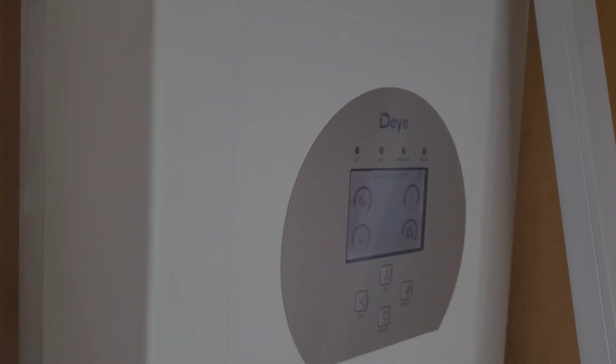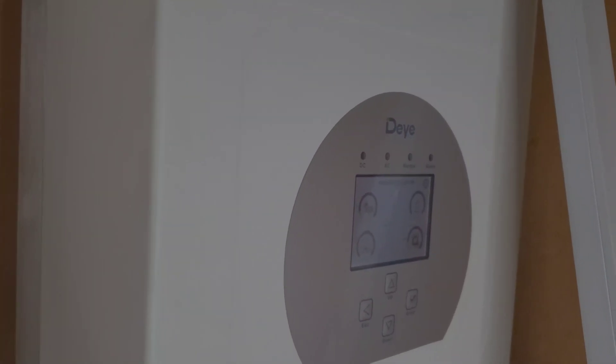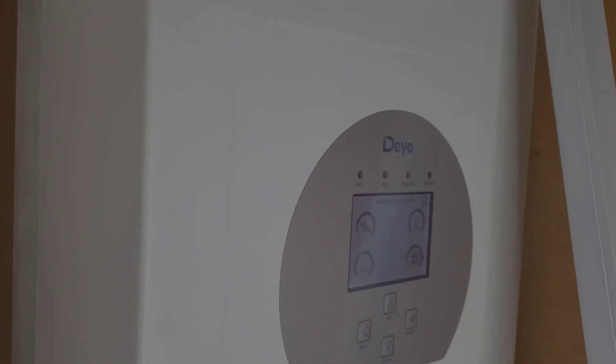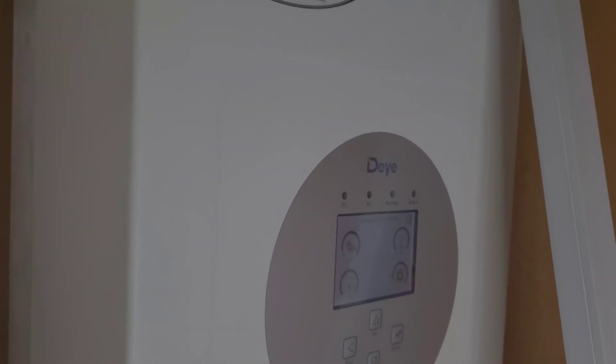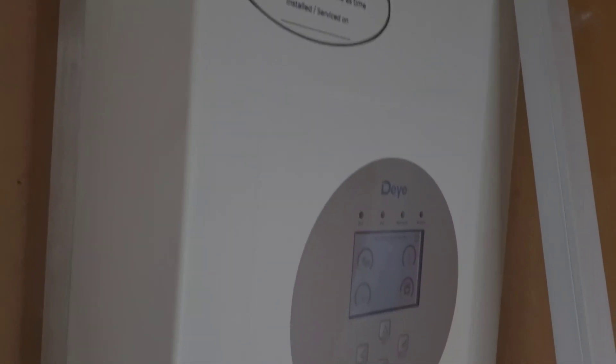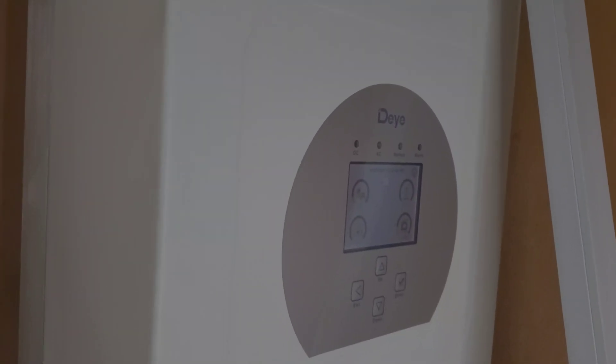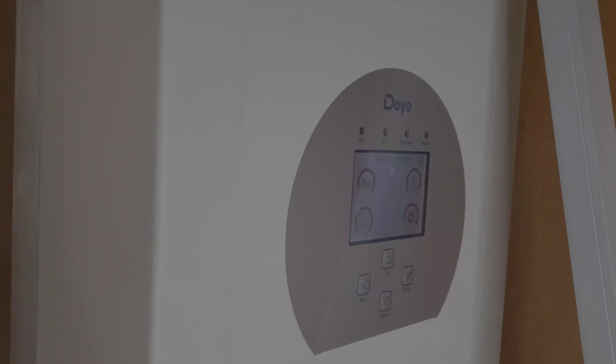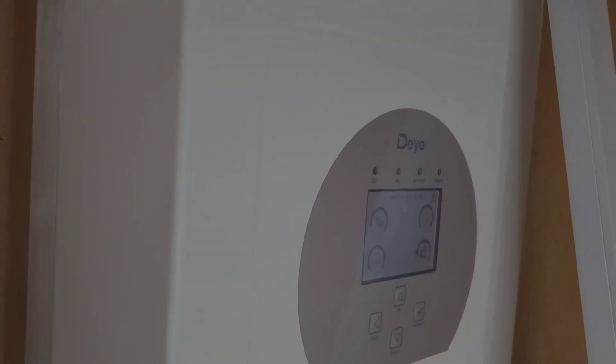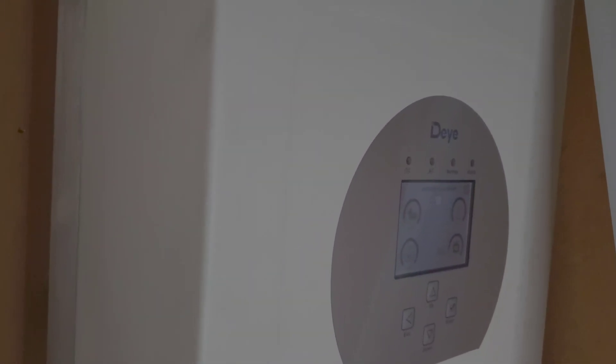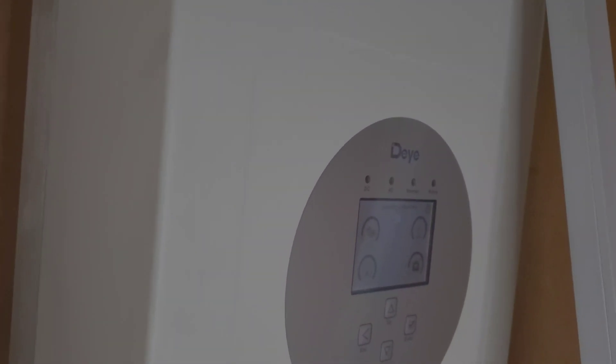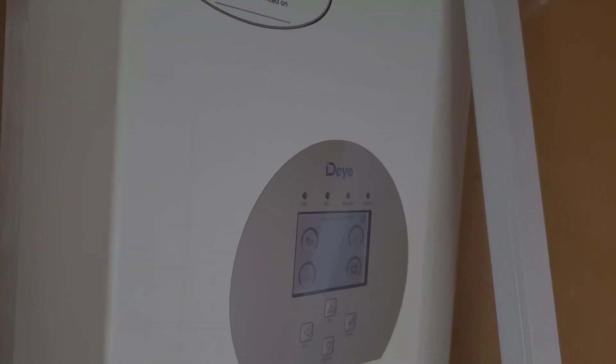So once the battery inverter forms the grid, that inverter comes on and starts looking for PV. It starts looking for production from the panels on the roof. Once it sees production, it does the DC conversion to AC conversion and sends AC into this inverter. Now there are multiple ways to do it. I can put it in front of the load but I don't do that. I'm putting it into the gen port.